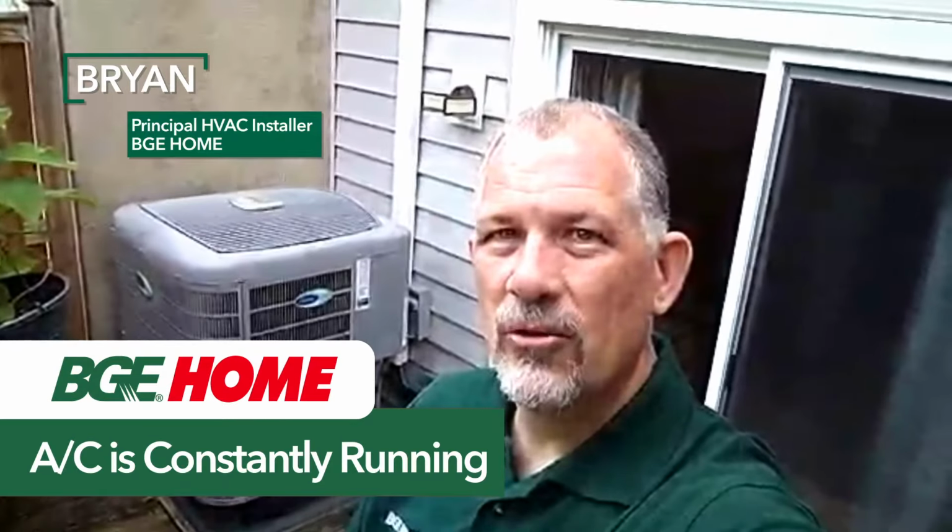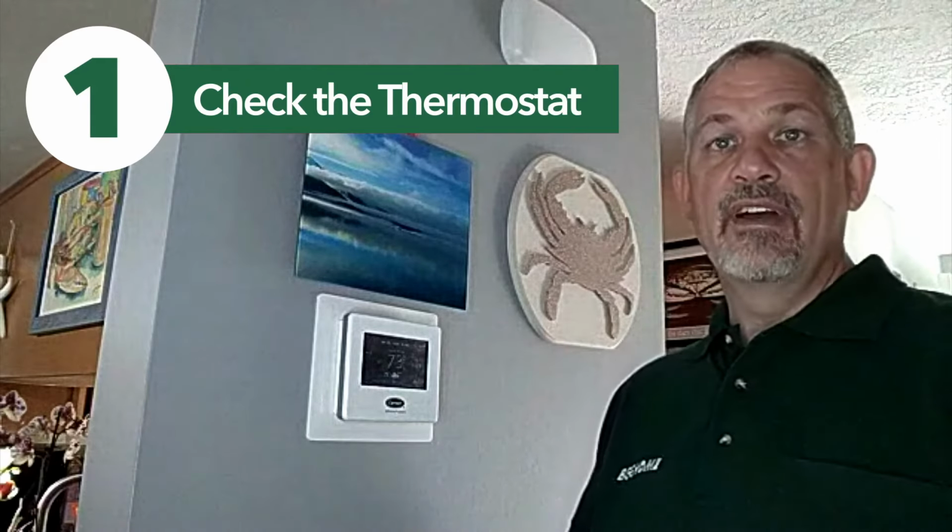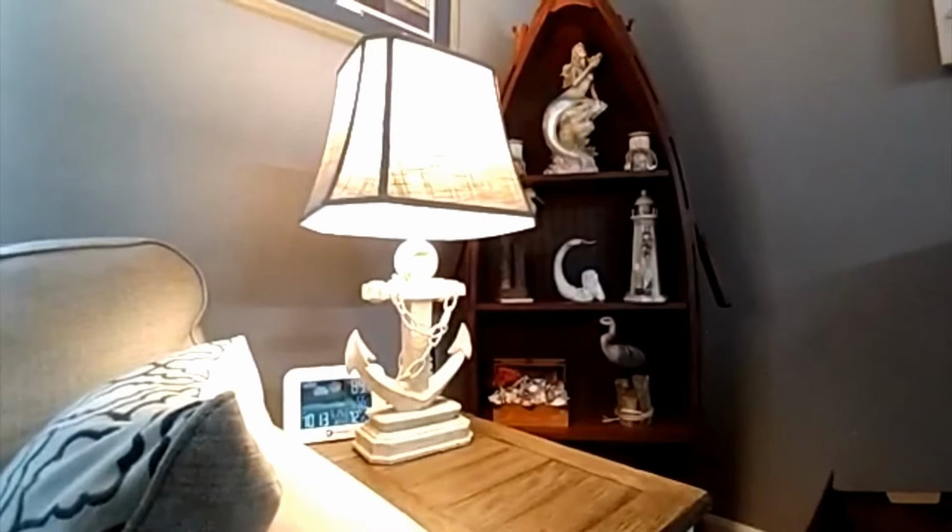Hello everyone, Brian from BGE Home here, and today we will go over what to do when your AC is running constantly. Check to make sure your thermostat isn't located near heat generating devices, like a TV or a lamp. These devices generate heat, which can cause your thermostat to detect a higher temperature than the actual temperature in your room. This will cause your system to run for longer than it needs to.